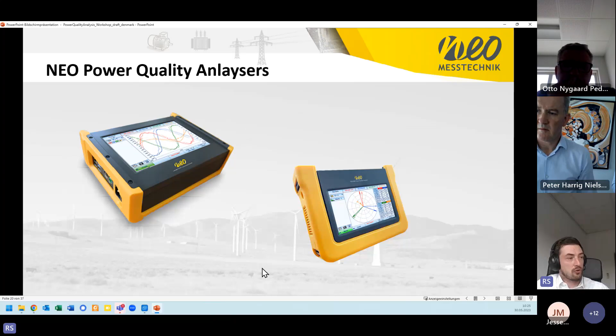For our mobile power quality analyzers, we have set up two solutions in the last years. The first is called PQA 7000. It's class A, with 40 kilosamples per second, so it's for the lower requirement, I would say. We have 4 voltage inputs, 5 current inputs, accuracy of 0.05%, and safety category 3 and 4 with 600 and 1000 volt. We have all the extended PQ functionalities because we use the same software and the same report analysis. The only limitation is bandwidth, but that also makes it cheaper.